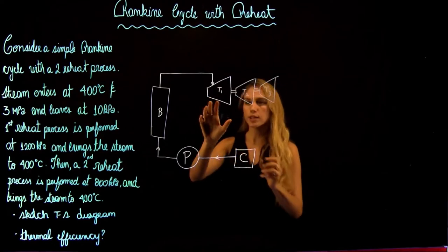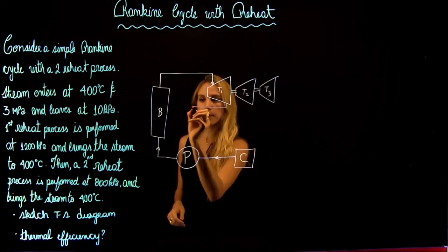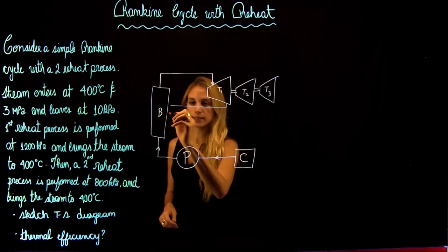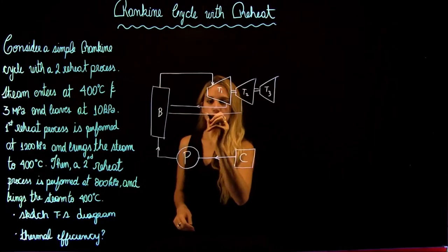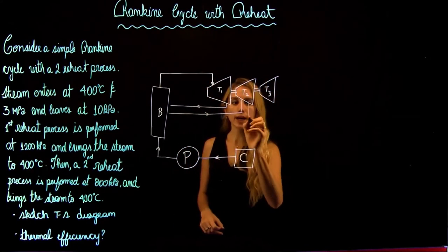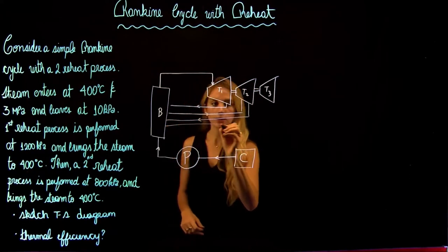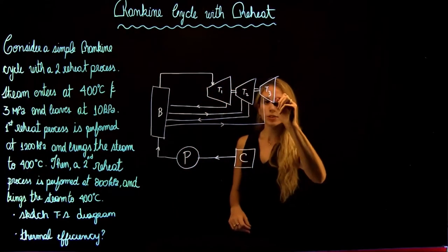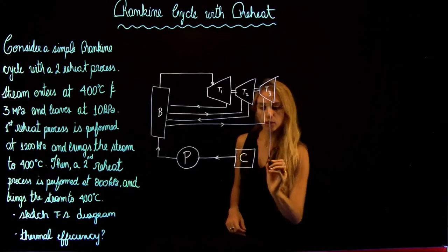In a reheat system, after the expansion of the first turbine, the steam is sent back to the boiler, where it is heated to reach the superheated state before being sent to the next turbine. This is the first reheat process. Then the steam from the second turbine goes to the boiler where the temperature increases before being sent to the third turbine. The steam then leaves the third turbine and is sent to the condenser.